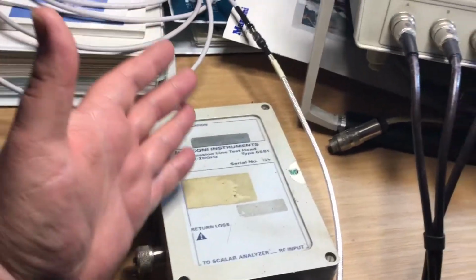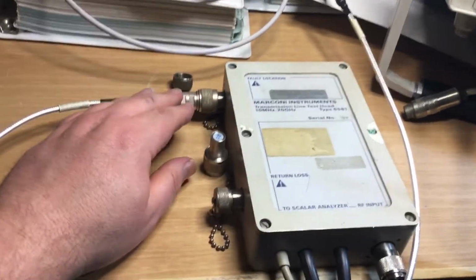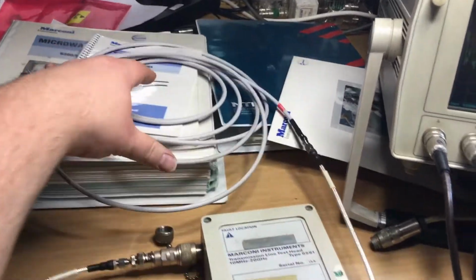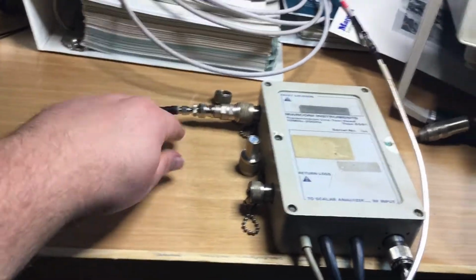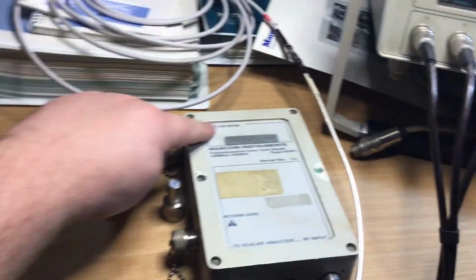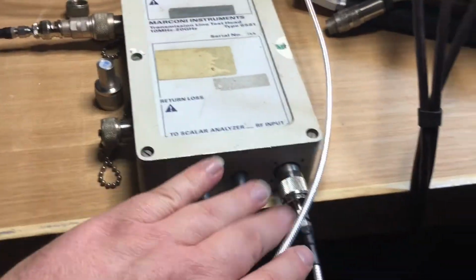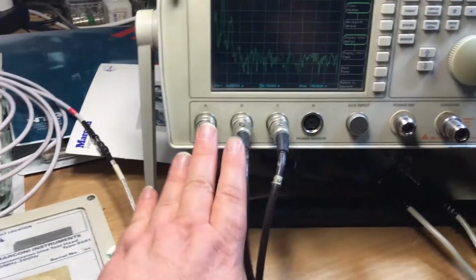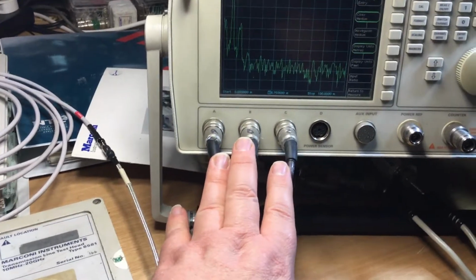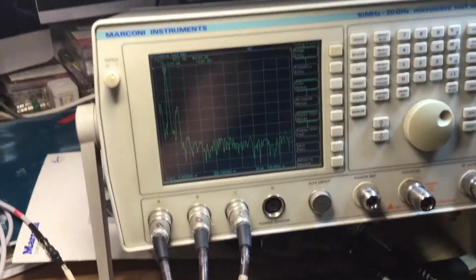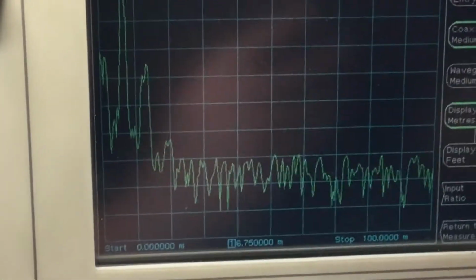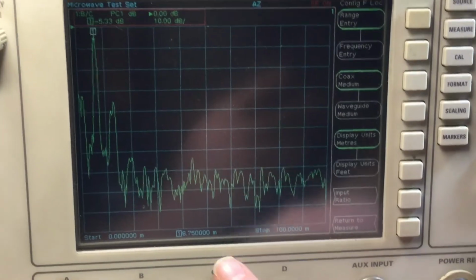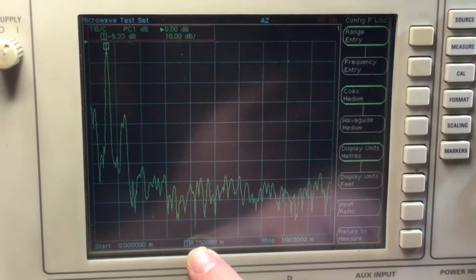So what we've done for this measurement, after I've calibrated this, is we've attached a cable, which is all this lot here, 7 meters of cable, to this port, which is a fault location port here, and we've connected the head up to the 3 inputs on the test set, A, B and C, and now we're ready to do a measurement where we can look at what we've got. So in the bottom of the screen, if I just zoom out a bit, you'll notice just there it tells you how many meters the marker is at, and I've adjusted the marker to show the peak there.